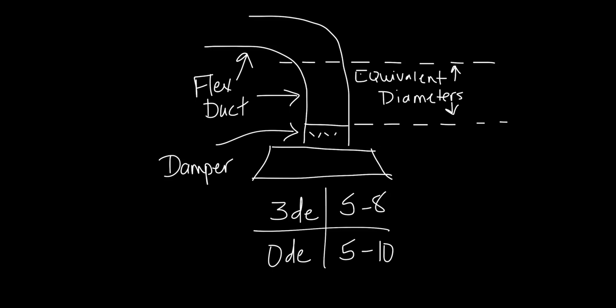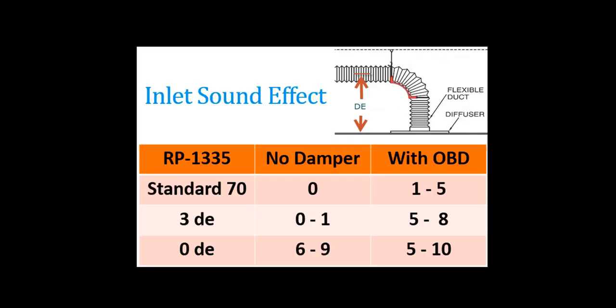Putting the data for the third case and the fourth case side by side points out some interesting trends. Notably, with no damper, there is little difference between the standard 70 installation and the 3 equivalent duct diameter installation, but there is a jump when you go to the 0 equivalent duct diameter installation.